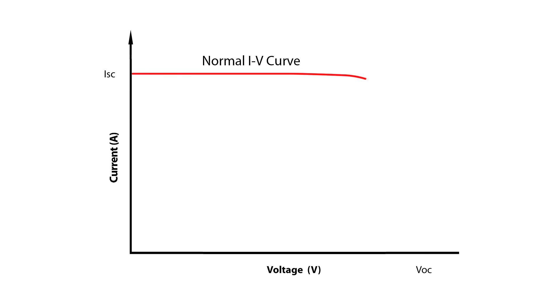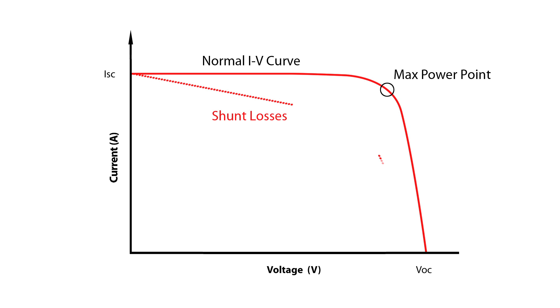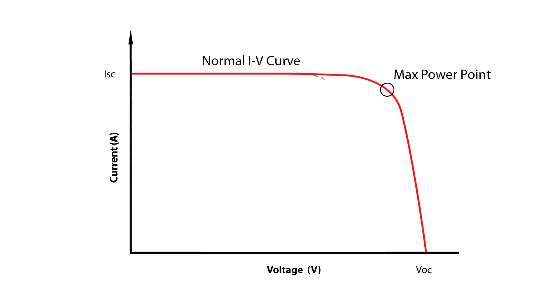A full IV curve trace allows the observation of PV performance at and around the maximum power point. Further diagnostic value is derived from examining the shape of the IV trace. For instance, the slope at the top of the curve will reveal possible shunt losses, and the slope at the right side of the curve will indicate the amount of series loss. Notches in the curve indicate mismatch, which can be caused by shading or other effects.